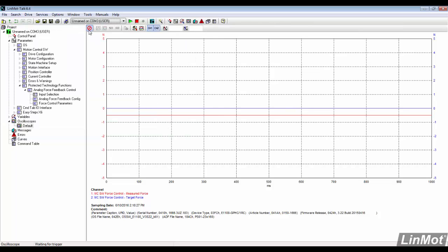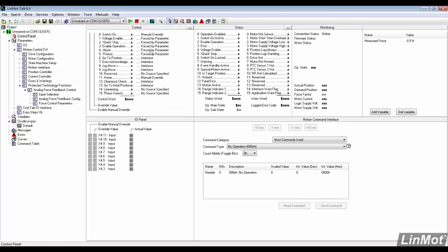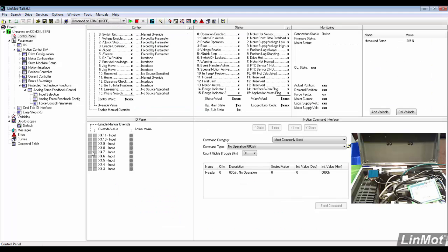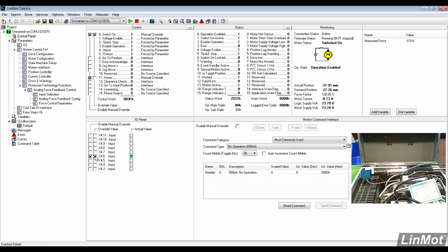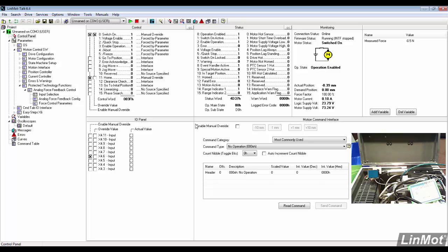We arm the oscilloscope and trigger the move. The rising edge of X4.6 extends the motor and then enables force control. The falling edge retracts the motor and resets the force control limits.